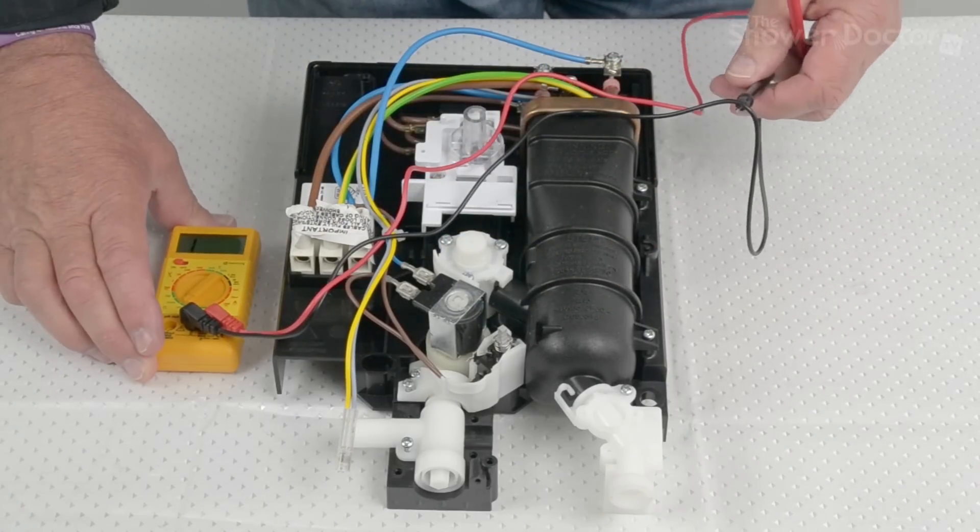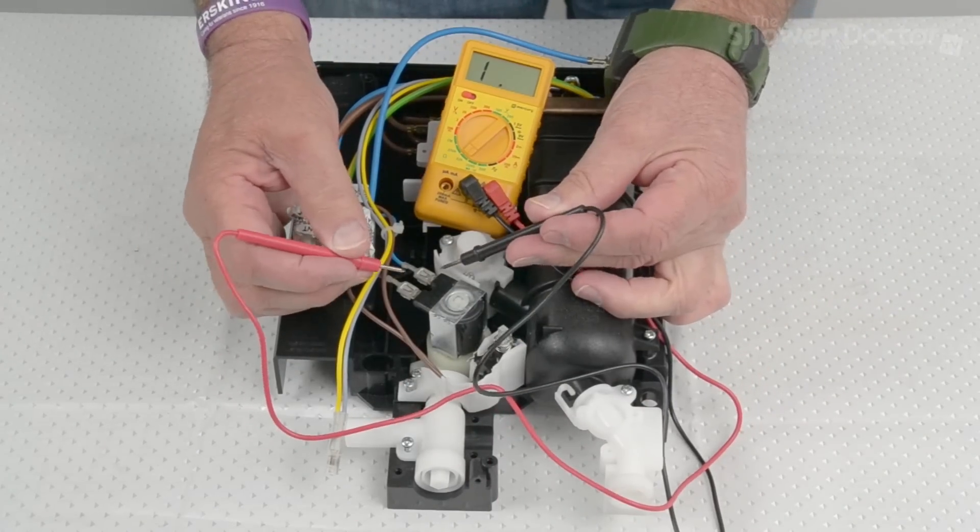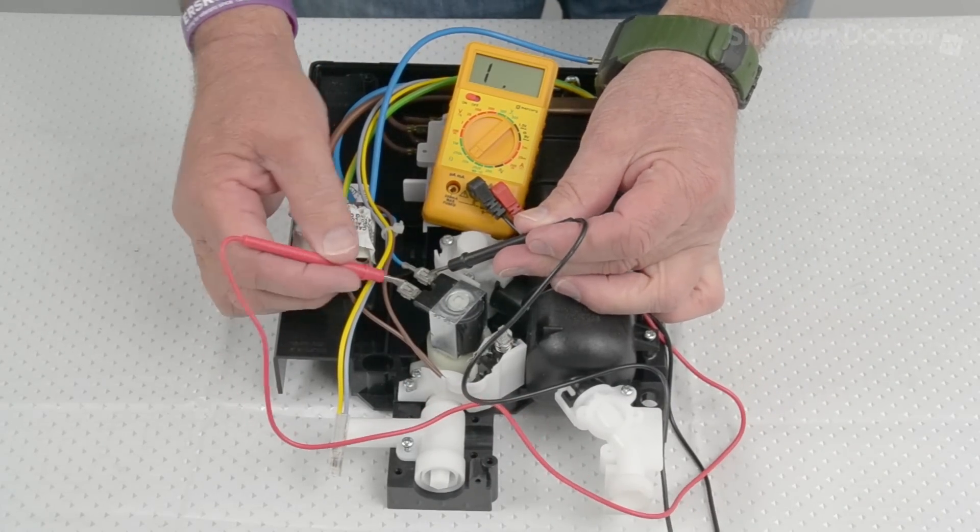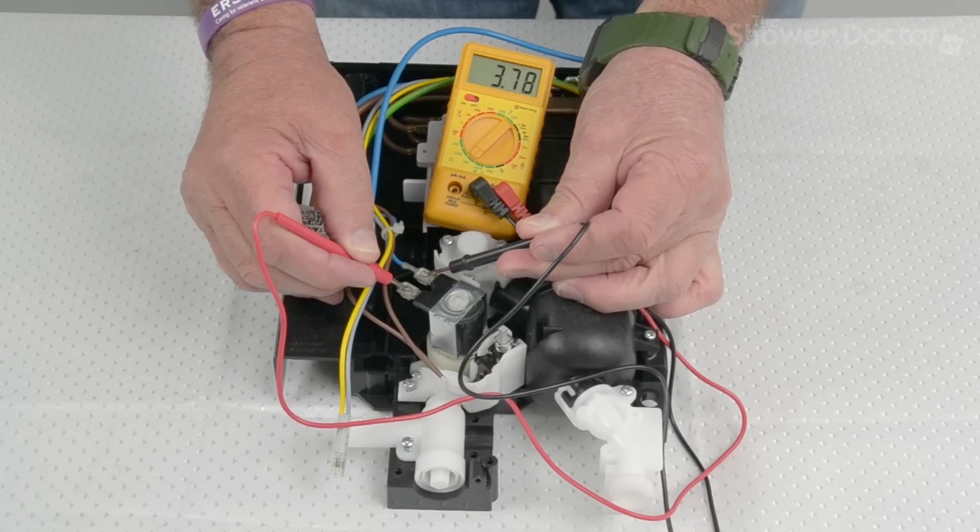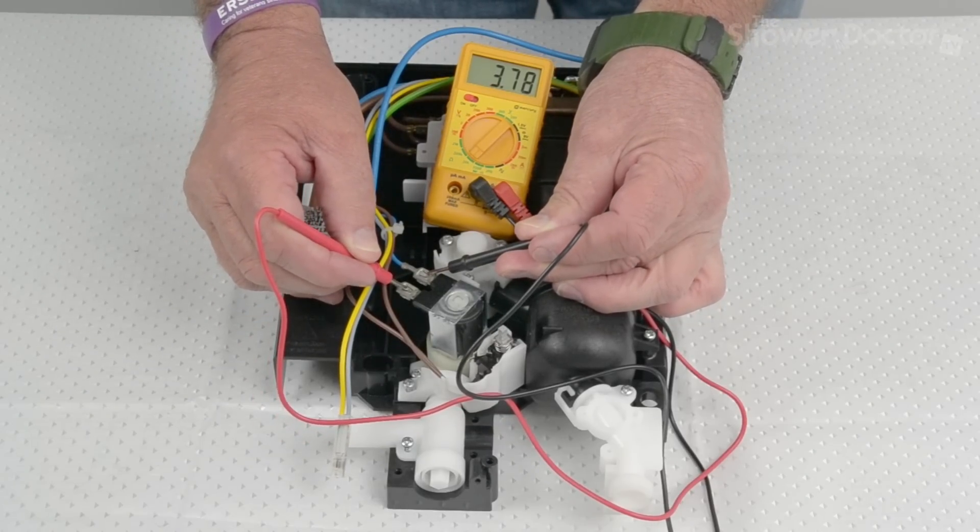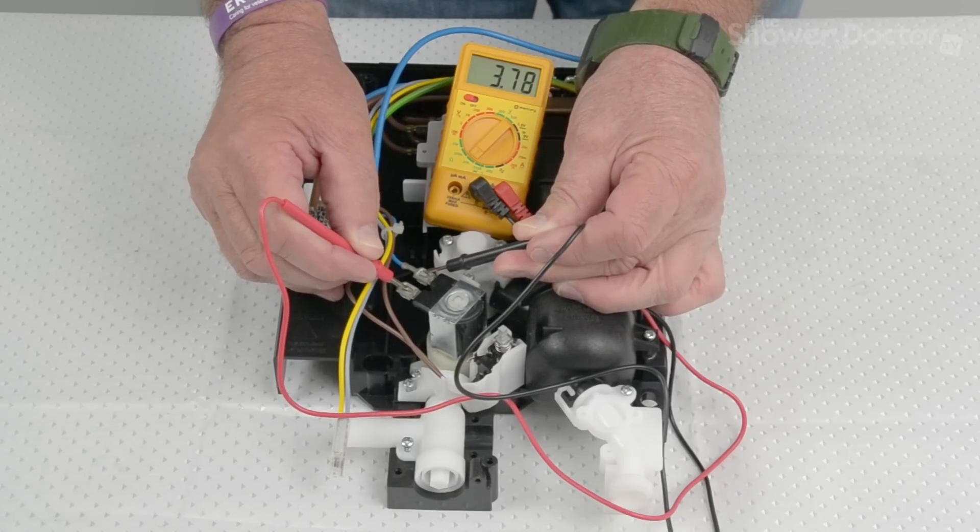And so I think we'll be able to leave that still there so you can see this. The polarity doesn't really matter as far as this is concerned because we're measuring resistance. And this solenoid has a resistance of 3.7 ohms. Basically anything over 3.4 and the solenoid is good.